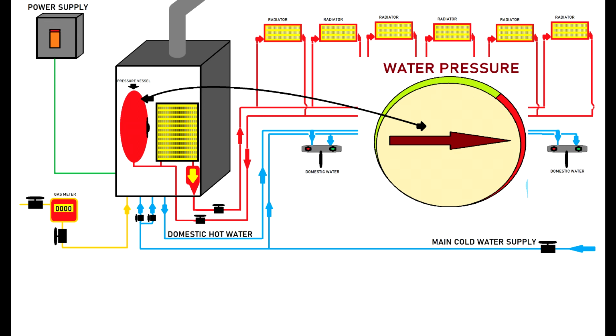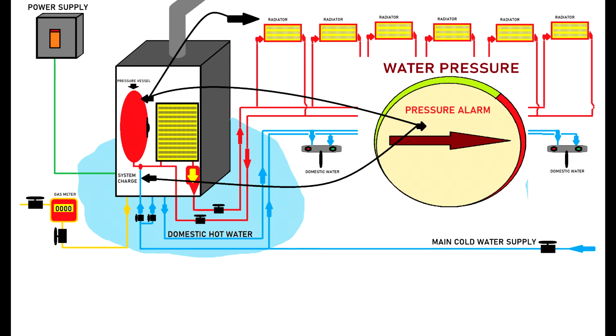However, after months or years the pressure vessel can lose its ability to hold the pressure, because the bellows rubber inside might be damaged or maybe it lost the air. So every year when an engineer does your boiler assessment, it is a good idea to check the pressure vessel, but I will not explain how to do this. A professional engineer will know how to do it. Too many radiators in your system will create the same issue. You have a good pressure vessel, but you have a huge volume, so the pressure vessel will be exceeded, and it will take volume up to the point where it can, then your pressure will increase, and then you will have a leak.